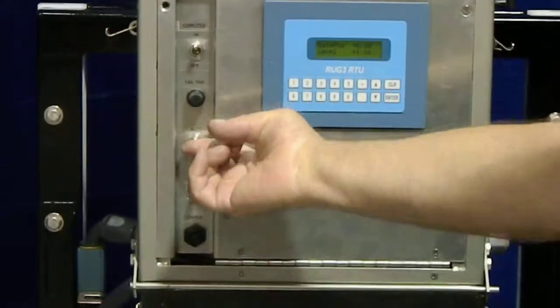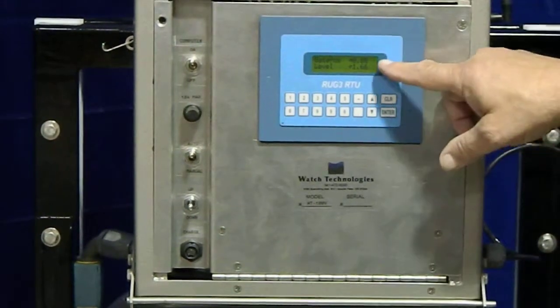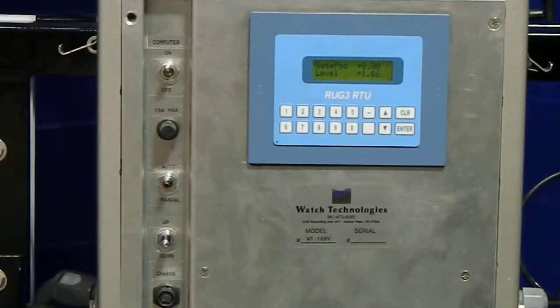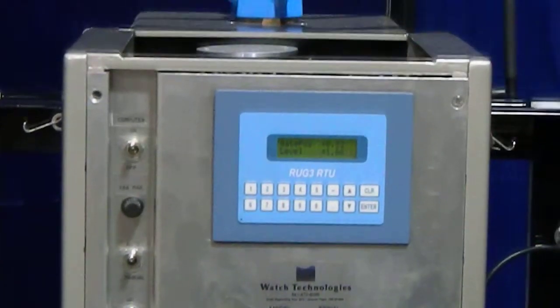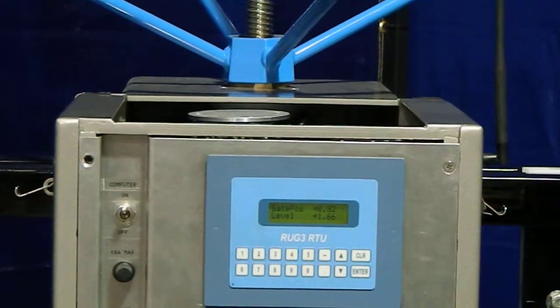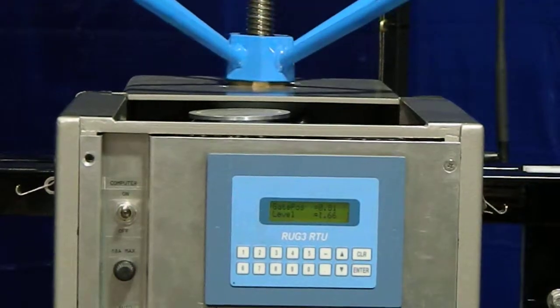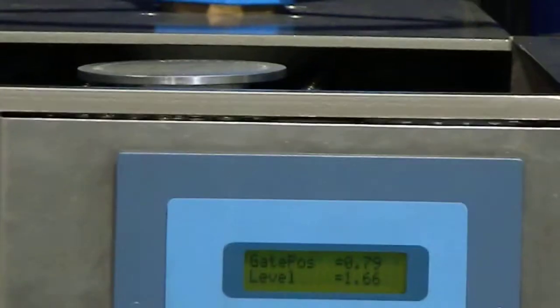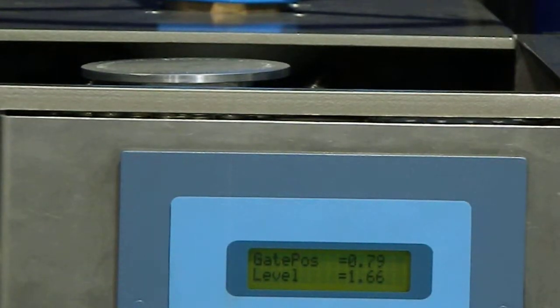Okay, so we'll put it in the auto mode. Right now we're reading 0.88. Our target is 0.8. So it's not far enough out to do the whole 5-second pulse, but it's going to do its job. Get there and stop. My goodness. Went past a little bit. But 1/100th of a foot is within the deadband, so it stopped.